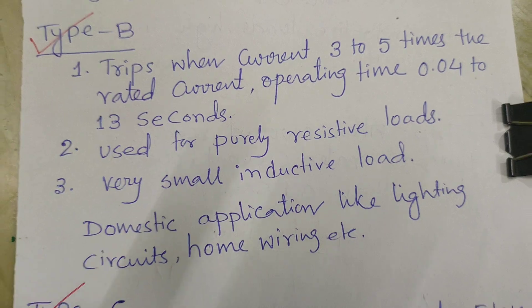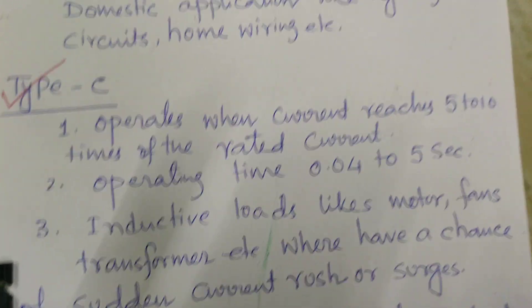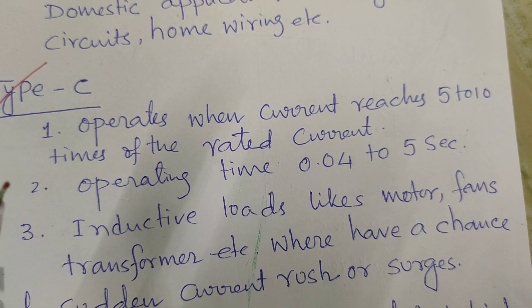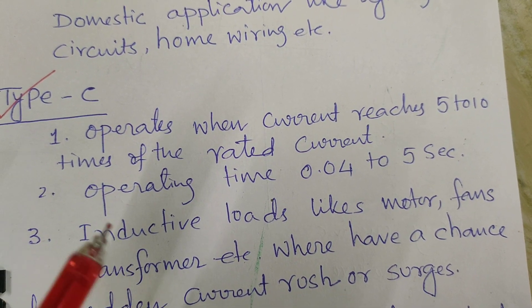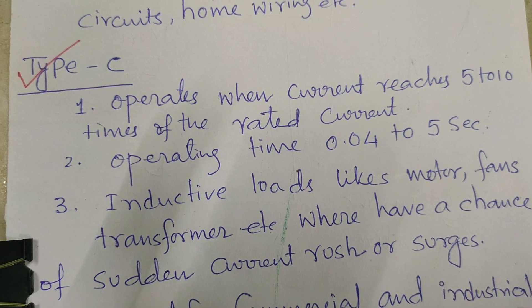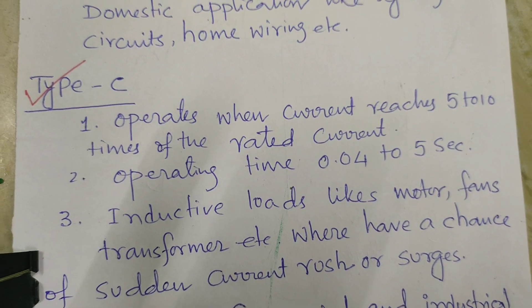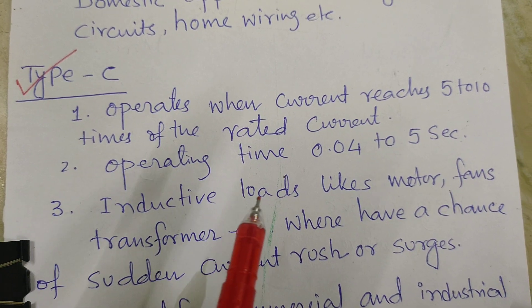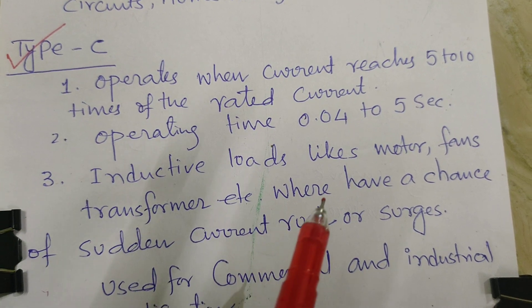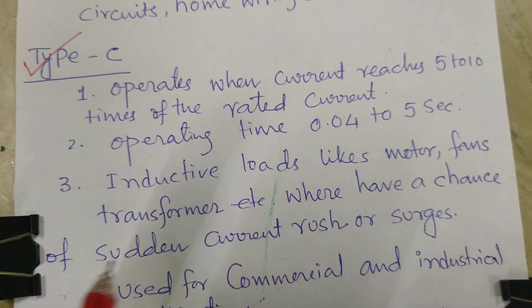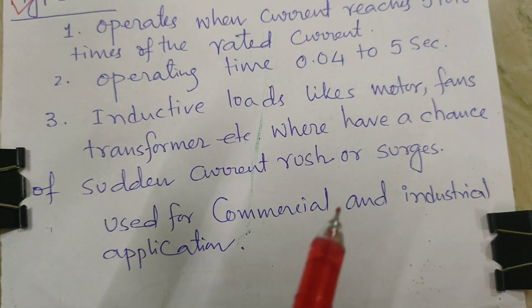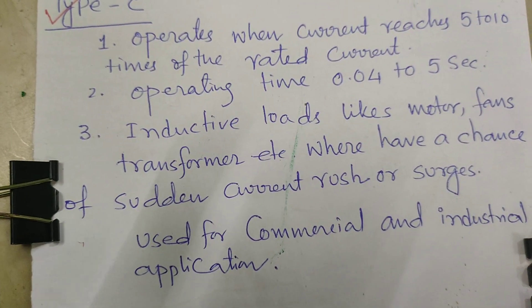C-type operates when current reaches 5 to 10 times of the rated current. Operating time 0.04 to 5 seconds. Inductive loads like motor, fan, transformers, etc., where have a chance of sudden current rush or surges used for commercial and industrial applications. C-type is being used for the commercial and industrial application.